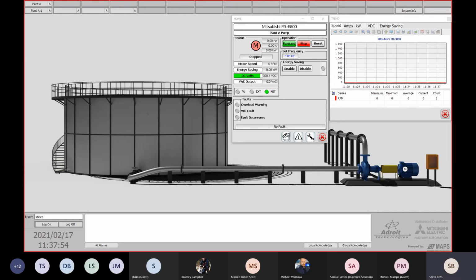So if I start the motor, it's going to ramp up to 50 Hertz. And as you can see in my graph or my trend, the motor started up to 50 Hertz, which gives me 1,500 RPM. If I look at my amps, currently I'm drawing 1.31 amps, and that I can also see on my trend. I'm using a 0.4 kilowatt motor, and at the moment, due to the motor being free spinning, I'm using 0.08 kilowatt, which is shown there. My DC voltage will stay constant because I have a standard supply to it. And my energy saving at the moment is 0.33 kilowatt.